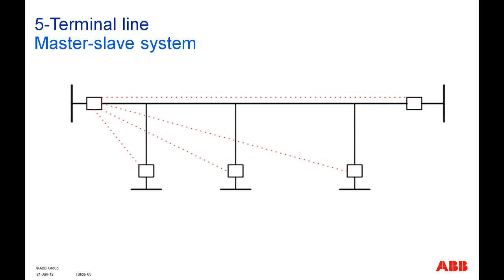In this master-slave system, only one box is acting as a master, and it is fetching all this information from all the other 4 devices. The tripping decision is done by the master, and then it is transmitted via this fiber optic link or the communication link to the other terminals to trip the circuit.